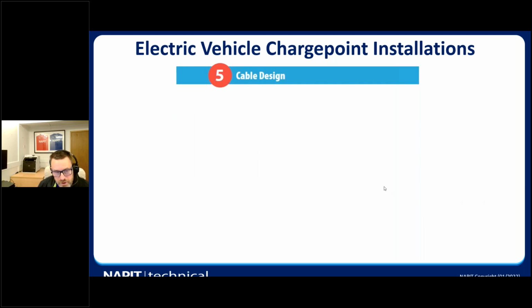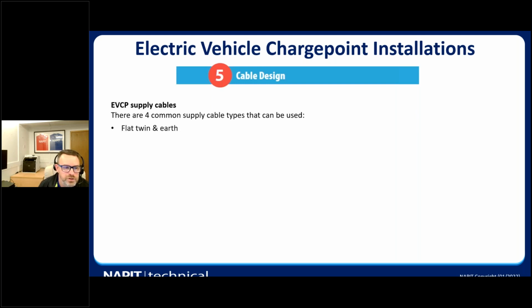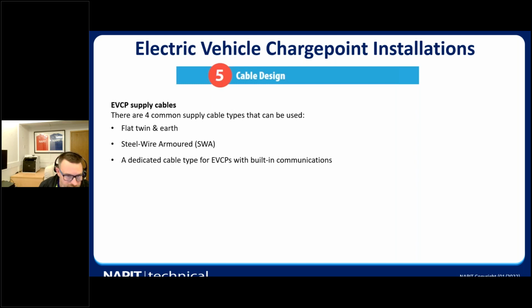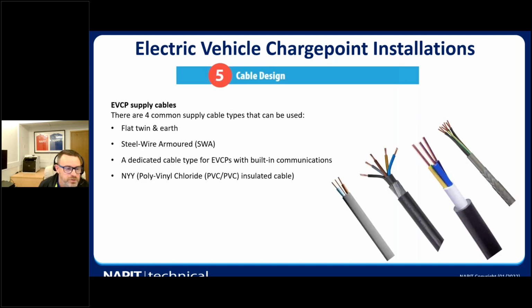Number 5 is looking at the cable design. It's important to look at what type of cable you're going to use for the installation and where it is. With EV charge points, there are 4 common supply cables that we've used. We've got flat twin and earth, we've got steel wire armoured, we've got the dedicated EV charge point cables with built-in communication cables, and we've got the NYY cable, which can be installed as well. Those are just examples of the types of cables. More and more we are using the dedicated EV cables with the built-in communications because it's one cable that can be installed.